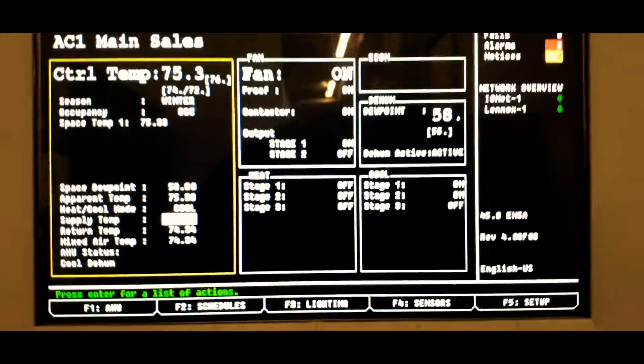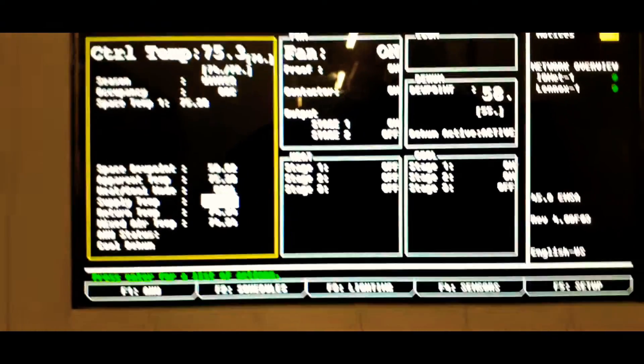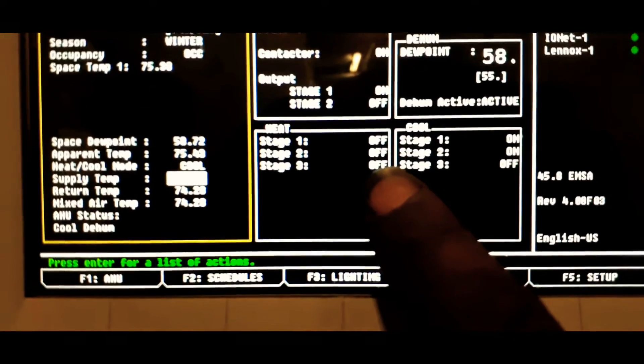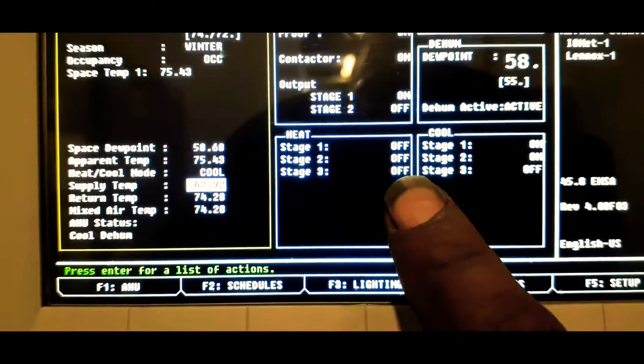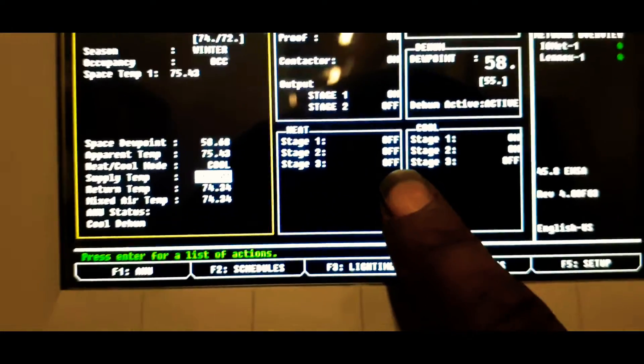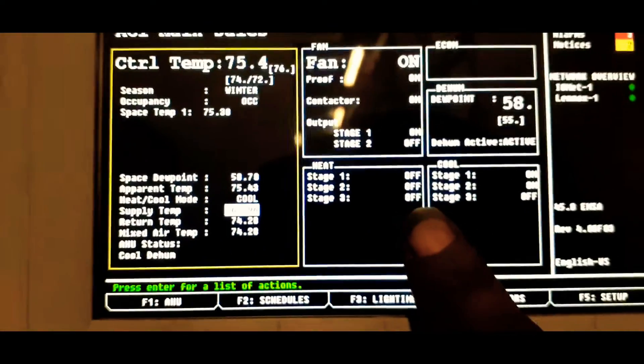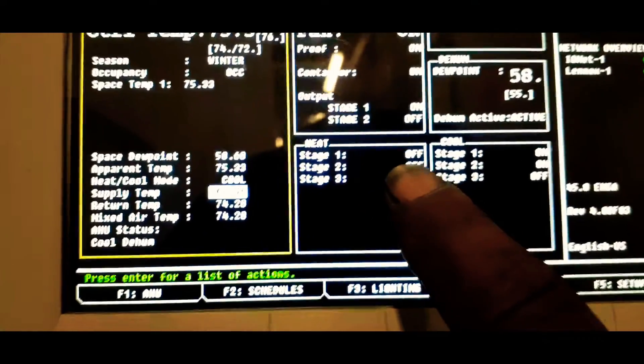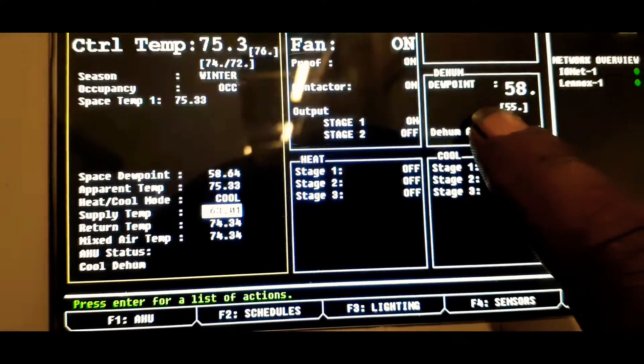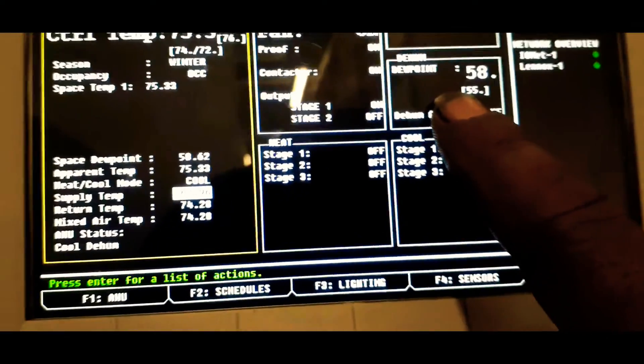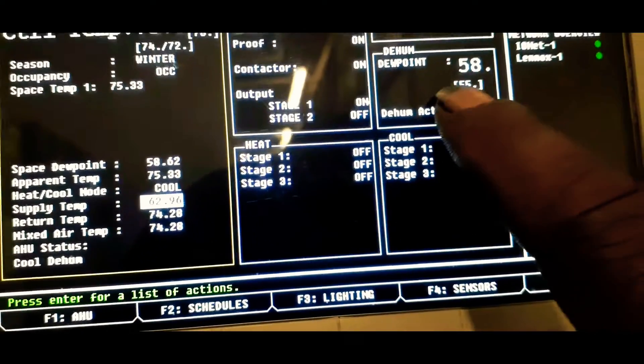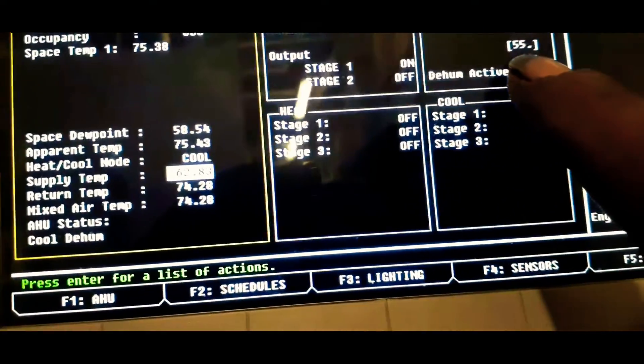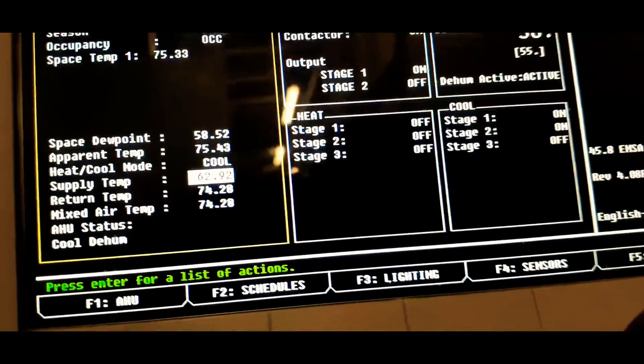All right, so our temp's dropping, and right now it says heat off. And that's mainly due to the heat reclaim is not running. Once we get down to 72 degrees, this will kick on and then we'll start drying out the air even more, the air. And as you can see, we just dropped another degree, dew point 58 now.